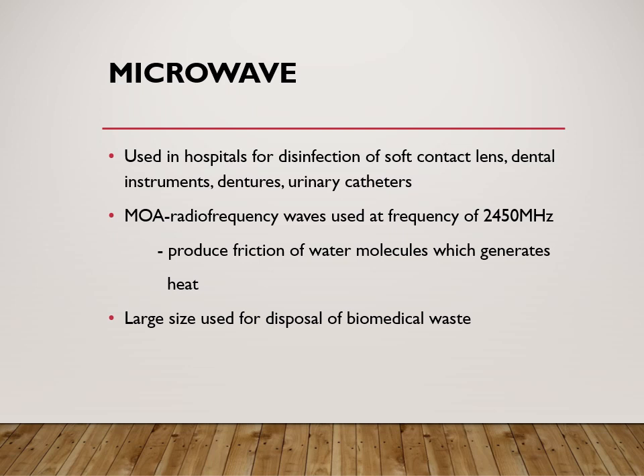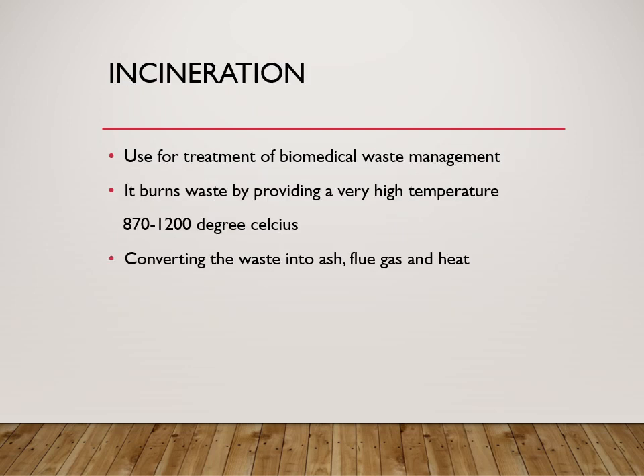Microwave sterilization uses radio frequency waves at 2450 MHz to produce friction of water molecules, generating heat; it is mainly used in biomedical waste management. Incineration also used for biomedical waste management, burns waste at a very high temperature of 870 to 1200 degrees Celsius, converting waste into ash, flue gas, and heat.